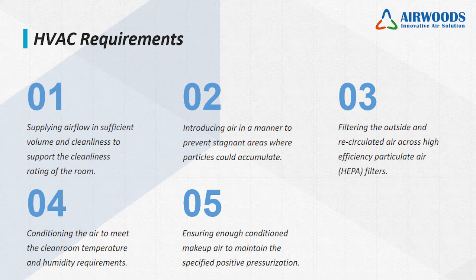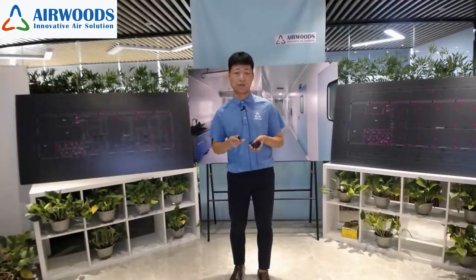The second one is introducing air in a manner to prevent stagnant areas where particles could accumulate. The third one is filtering the outside and the recycled air from indoors, through high efficiency particulate air filters with a HEPA filter, okay? The fourth one is conditioning the air to meet the clean room temperature and humidity requirements. The last one is ensuring enough conditioned make-up air to maintain the specified positive pressurization. So these 5 parts are the main requirements for the HVAC system design.